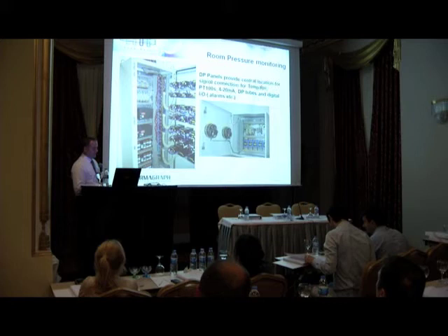Just on the temperature and humidity monitoring, I touched upon it. You've got a room probe, which is a single unit, but you can have one of these remote probes, which can be connected to the HAC particle counters, or to a wall unit. Typically this is a probe that will sit inside your incubator, rather than the whole device. They're typically accurate to about plus or minus 2% over a range between 0 and 90%. Actually, I think it's 0 to 95%, but most sensors aren't very accurate from 95% to 100%.